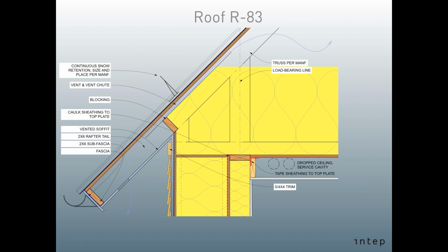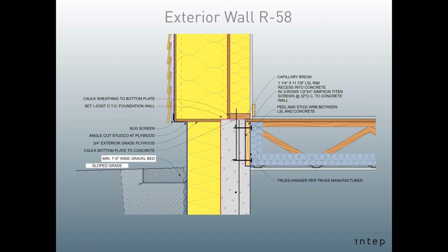So again, just a bunch of good common practices, more of it in that our insulation blanket up here is about 2 feet thick. It'll later settle down to about 20 inches over time. And that roof has an R value of 83. I think the wall one was shown on there, 58. So that gives you an idea. So there's a slight progression of R value.